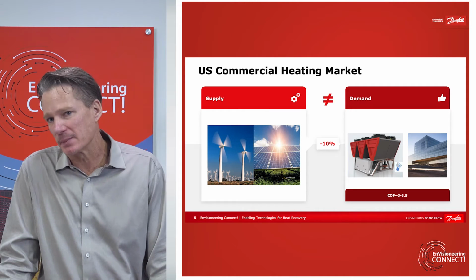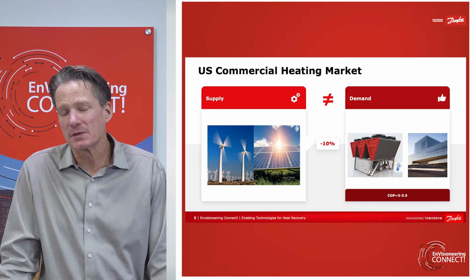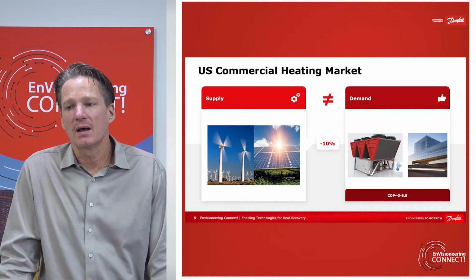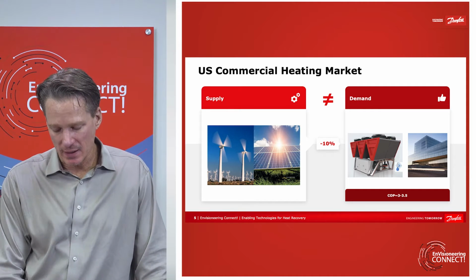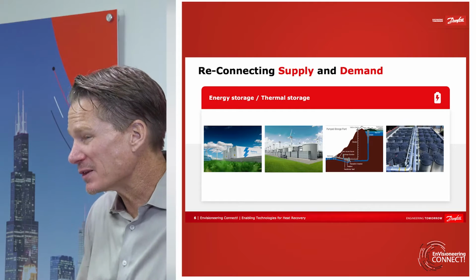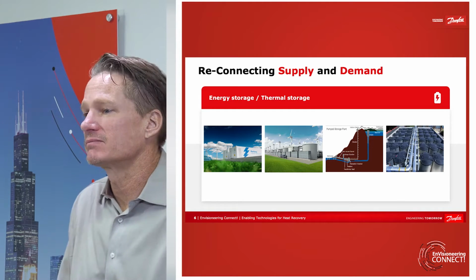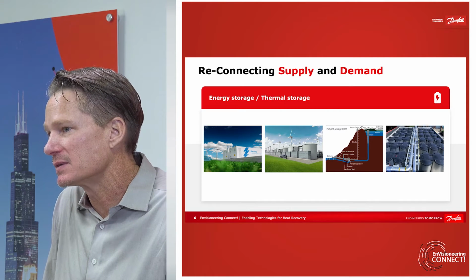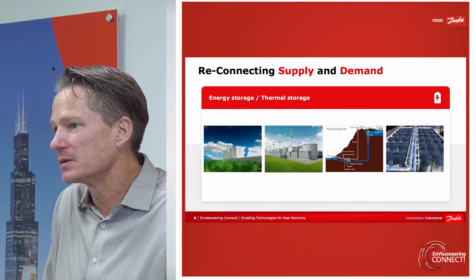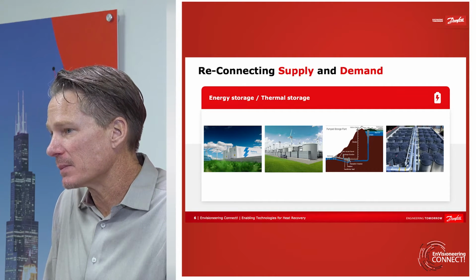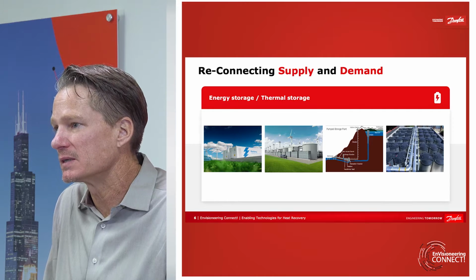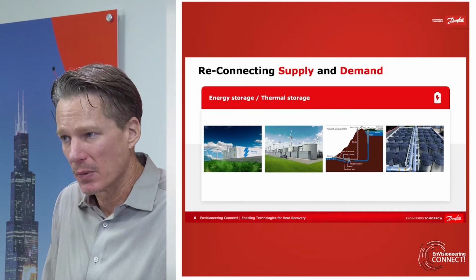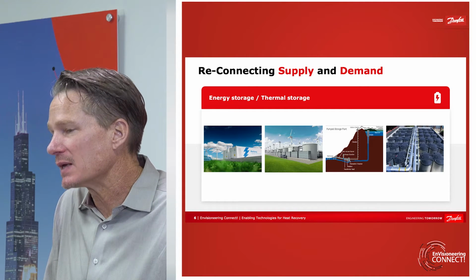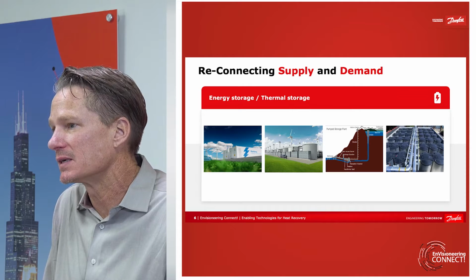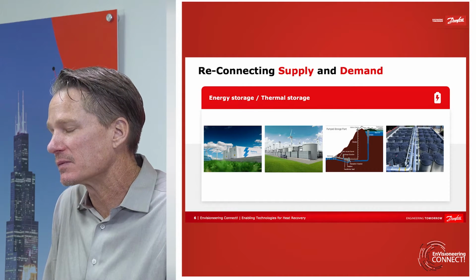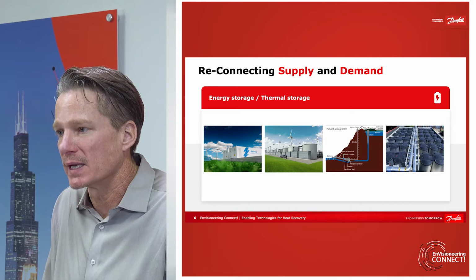It's grid level storage, it's demand side storage, it's building storage. Any form of storage addresses that disconnect, and I'm going to talk again later about why that's critical. But storage takes many different forms. It includes battery storage, pumped hydro storage, and thermal storage. That's the other thing that's going to come into play in the future, and what you're seeing in the last 5 years is a significant growth in thermal storage usage, both hot storage and cold storage. And it corresponds to the same driver of renewables integration into the grid and decarbonization and the potential for heat recovery and heat pumps. So that's the main takeaway: it's all tied together.